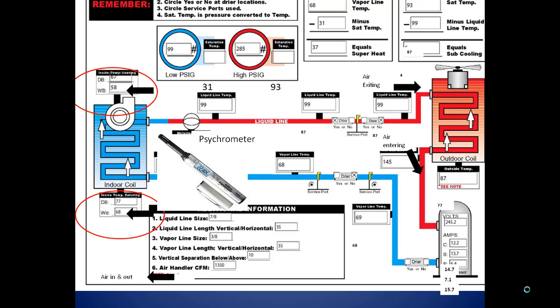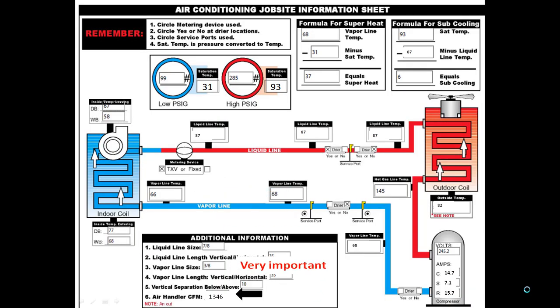We need to make sure we're taking the air readings in and out on the condensing unit. And the very important thing that you can take here, like I said, very, very important, is the correct CFM readings. This is not a guess. This is not going by 400 CFM per ton. This is the actual CFM that air handler is putting out.